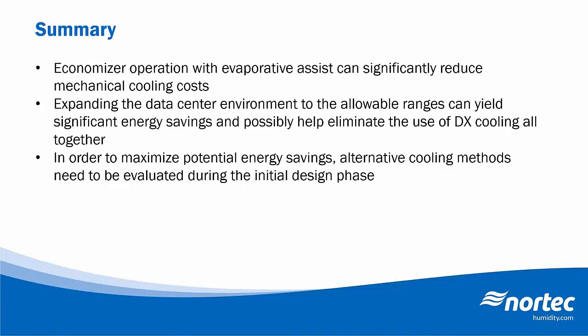So just to summarize here, it's clear that there are significant energy savings available from the use of economizers with evaporative assist, and potentially even more savings available if the operating range for the data center is opened up to the actually allowable range for temperature and humidity. But it is important to keep in mind that, really to maximize these savings, you need to evaluate this type of system in the initial design phase to maximize those savings.